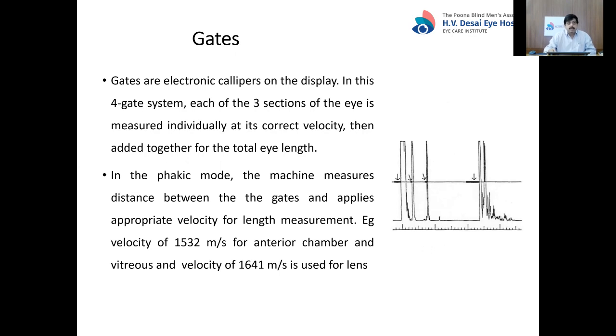Gates are electronic calipers on the display. The biometer places gates at every interface. In a four-gate system, each of the three sections of the eye is measured individually at the correct velocity and then added together to find the total axial length — gates at the cornea, anterior lens surface, posterior lens surface, and retina. In the phakic mode, the machine applies the appropriate velocity: 1532 meters per second for the anterior chamber and vitreous, and 1641 meters per second for the lens.